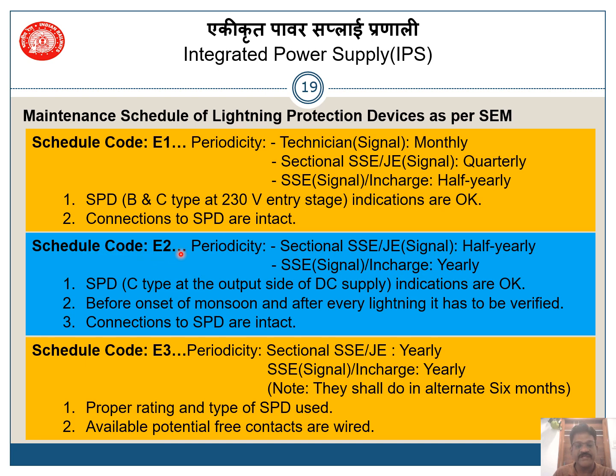While schedule code E2, here the sectional SSE is half yearly, while in charge SSE is yearly. What needs to be checked once in half yearly? SPD C type at the output side of DC supply, indications are okay. Before onset of monsoon and after every lightning, it has to be verified. So whenever there is sudden rain or sudden lightning, it is better to go and check the protection provided there. Connections to the SPD being intact or not shall also be checked.